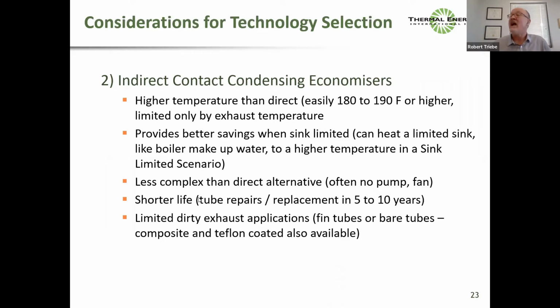So it is less complex than a direct alternative because it often can be installed just like a feed water economizer. So, you know, your water's already got pressure. It doesn't lose the pressure going through the economizer. In a direct contact system, because you shower over the water, you end up with a sump full of water, which then needs a pump. And a direct contact system has a higher pressure drop. So an indirect system can be less complex. No fan, no pump in many cases.